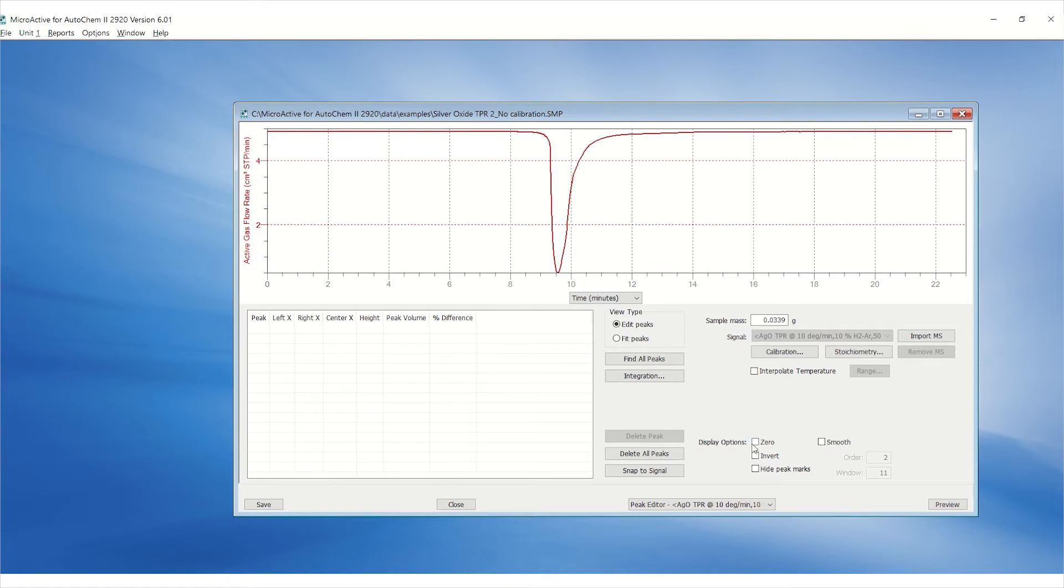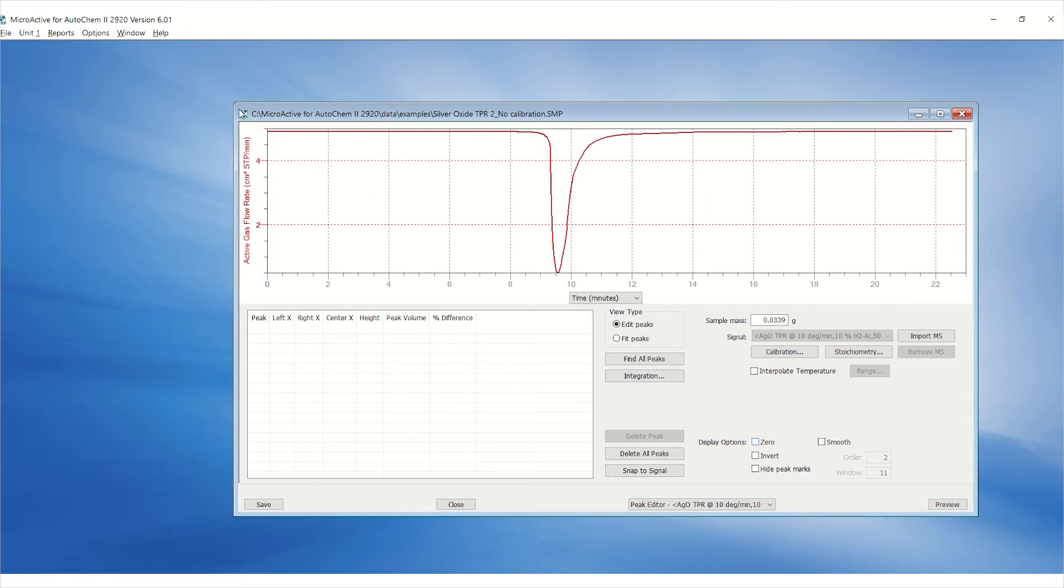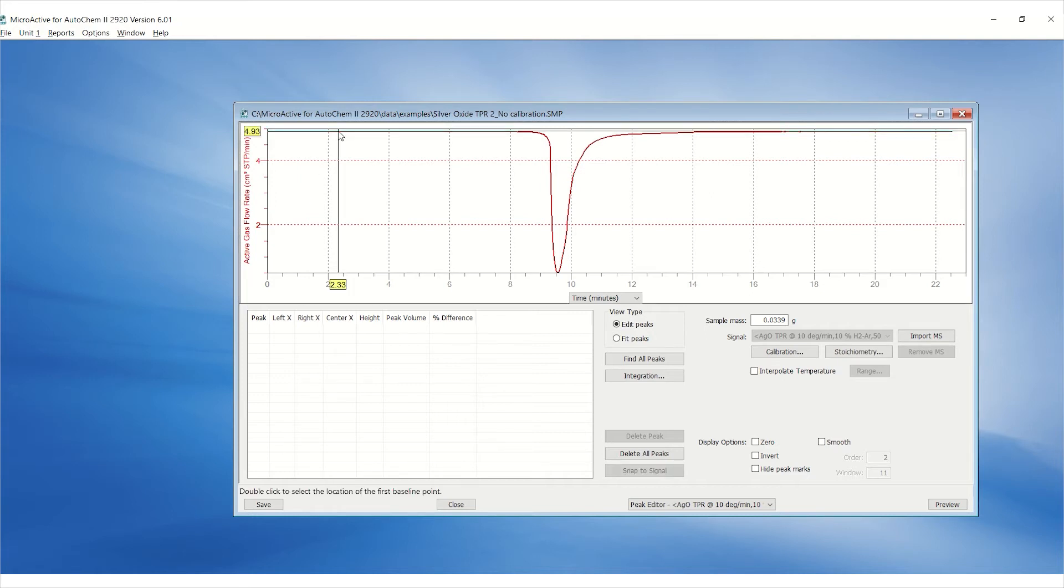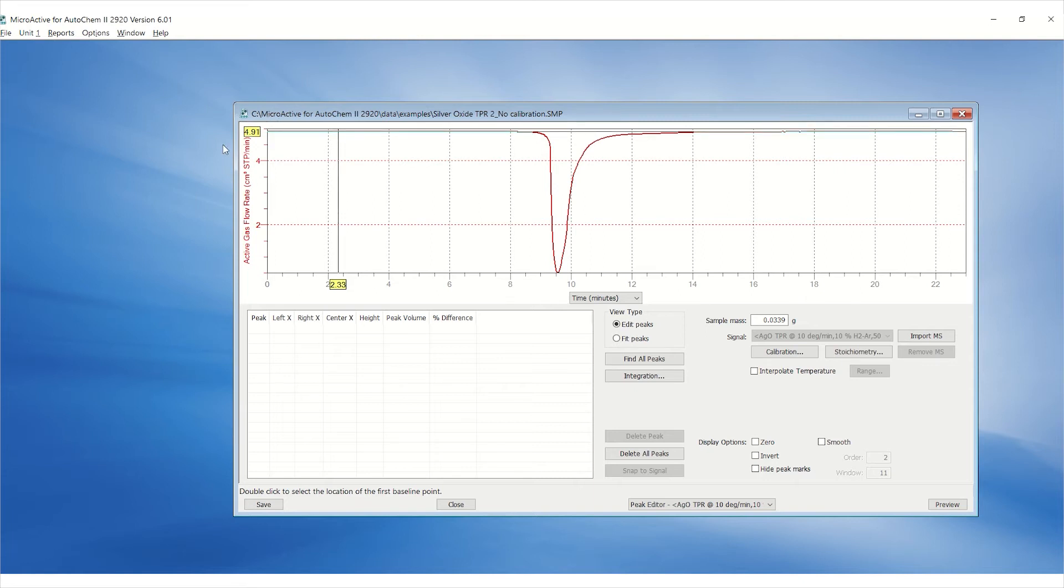Once the calibration is selected, the y-axis label indicates active gas flow rate in cubic centimeters per minute at standard temperature and pressure. Also notice the baseline is at 5 cc per minute, which is expected since 10% hydrogen argon is flowing at 50 cc per minute.